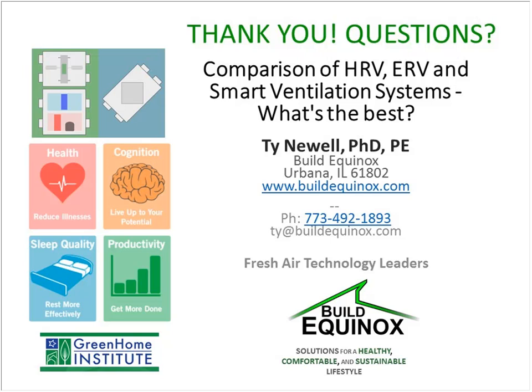As far as the sensors, we are among the first to incorporate these sensors. For example, the VOC sensor that we use is one that Honeywell now uses in their system, but we used it before they started using it. We took that as a good vote of confidence that we had picked a good sensor, and we have been running these sensors for about 6 years now. It's hard to say, accelerate the aging process on them. So yeah, we watch them very closely to see if they're going to deviate or have problems. But at this point, knock on wood, they all look great. But we're prepared to take care of them if they don't.